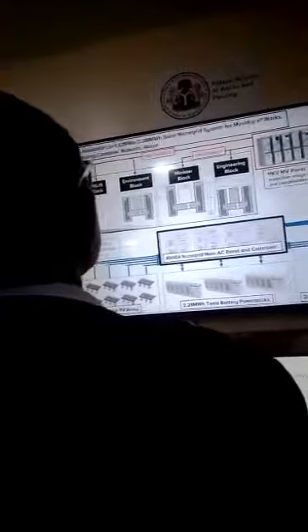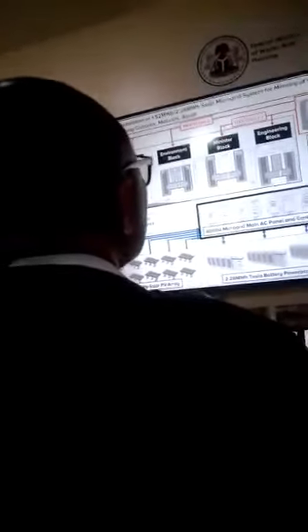But it now depends on the type of synchronization. We'll get to that. That one is a bit more technical, because synchronization requires all the energy resources to operate at the same voltage and frequency. And there's no way you can predict the voltage of the grid. So synchronization in generators is easy, because you can use the AVR and the governor to change the frequency and voltage of the generator to meet the requirement, so all of them synchronize at that voltage and frequency.